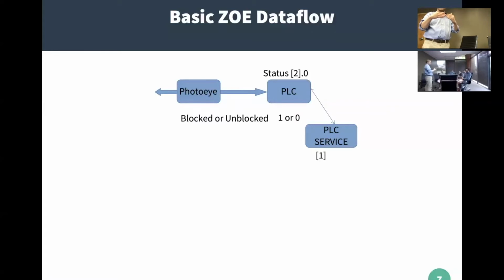And then the last dint is also the version number. And the reason for that is so that the PLC service can tell that it read the entire thing. Because if it lost communication halfway through, it knows that that chunk isn't the whole thing. So we have a couple checks there to make sure we grab the whole data and that it's the current version of data.